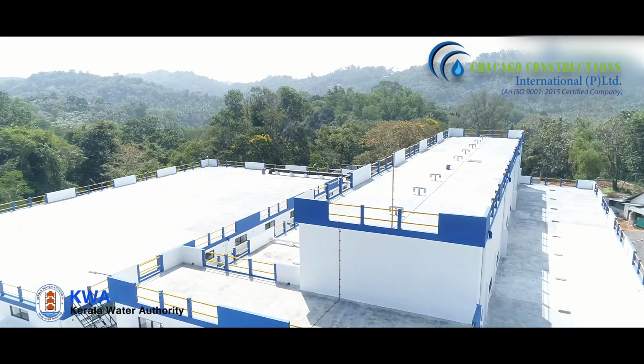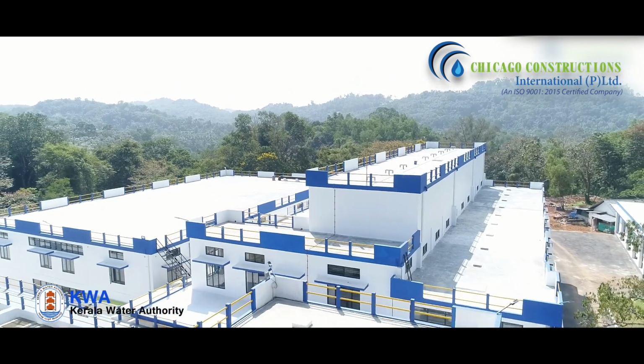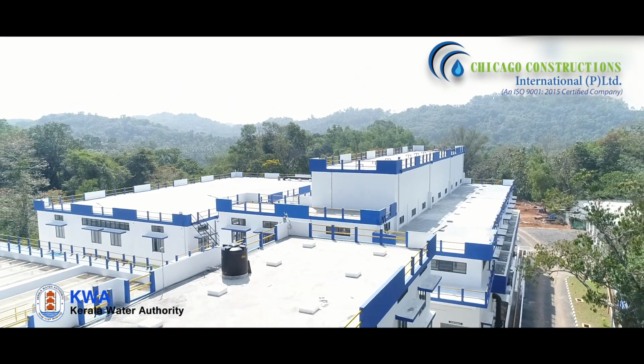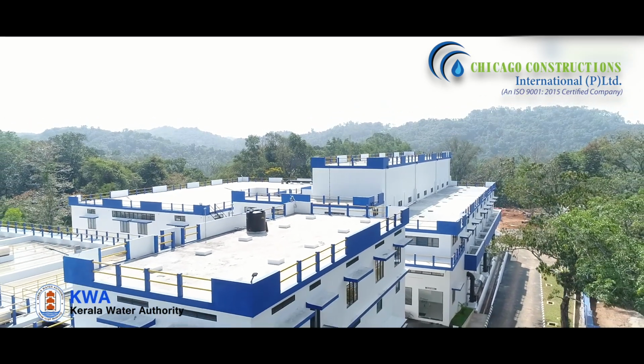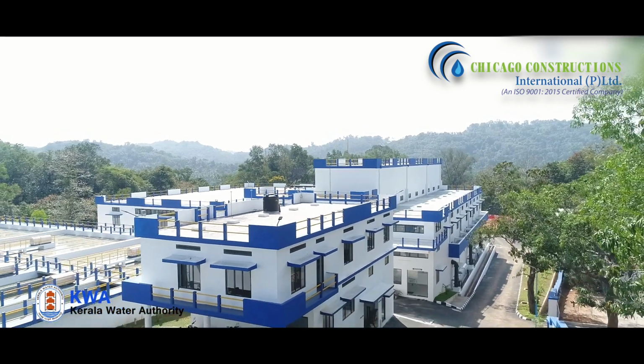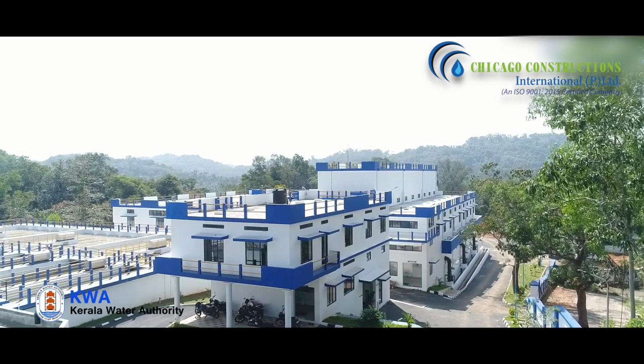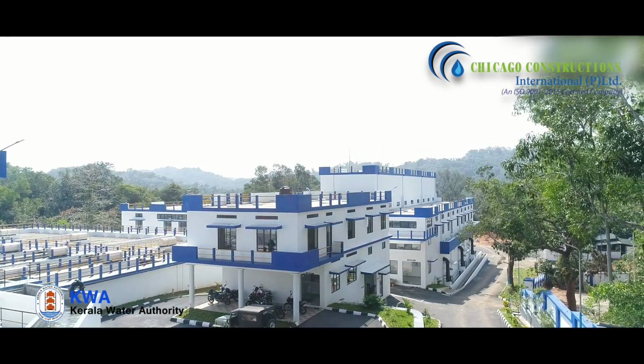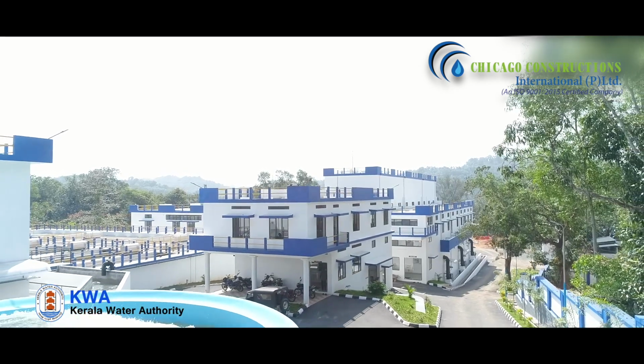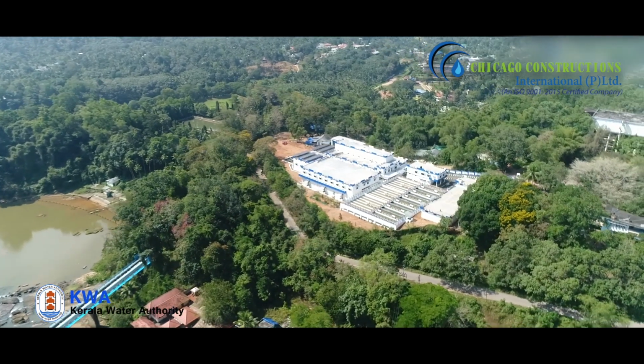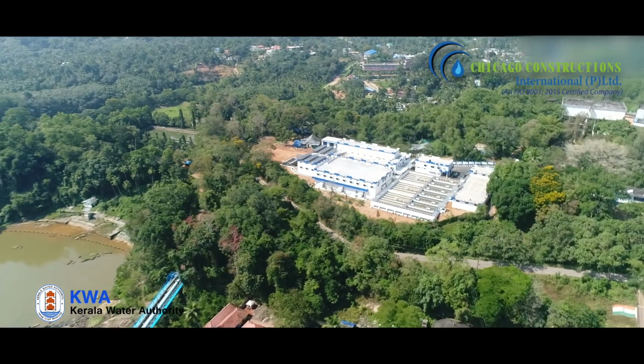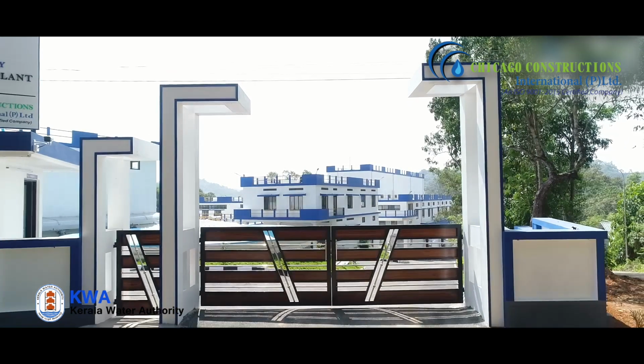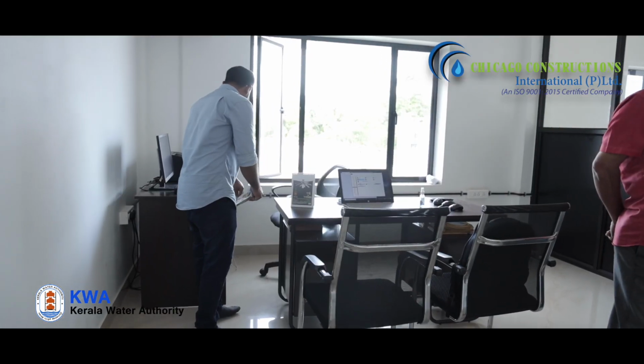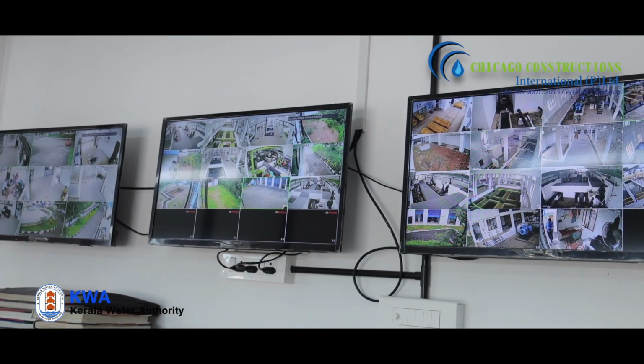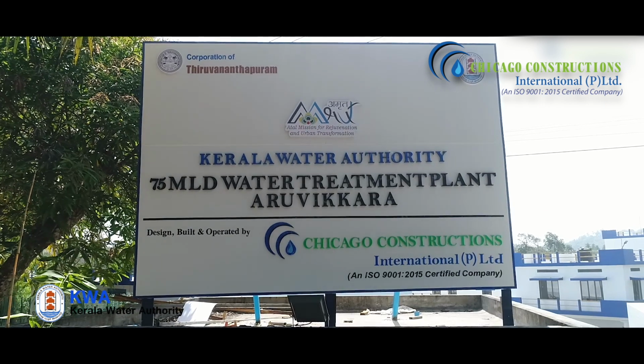The plant is designed by Chicago Constructions International Pvt Limited with the approval of WASCON, the design wing of the Kerala Water Authority. The 5-year operations and maintenance of the WTP is also being attended by Chicago Constructions International Pvt Limited. The plant is situated on a 3.5-acre campus, which includes a chemical store, chemical house, pump house, office building, laboratory, blower room, and SCADA room. From here, 75 MLD of fresh water is supplied daily to the Thiruvananthapuram Municipal Corporation. Qualified technical operating staff and chemical experts are working on a 24/7 basis for the continuous supply of treated water from the plant.